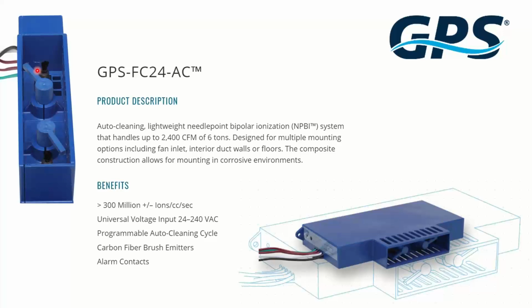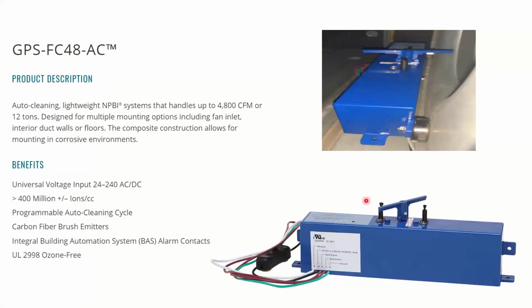You don't want debris or dust to build up on the needles because then it can't cause that electrical reaction, since it's basically blocked by the dust. So you've got to clean the needles off periodically. You don't have to do it daily, but this product just does it on a daily basis. Swish, swish. This one's got more of a helicopter thing, but it rotates and knocks both of them off, and away you go. Installation is really easy. If you get one of these, let me know. I'll send you a video on how to install it. You'll notice on these slides, on all of them, it says UL 2998 ozone free.